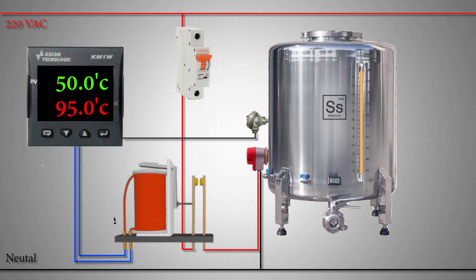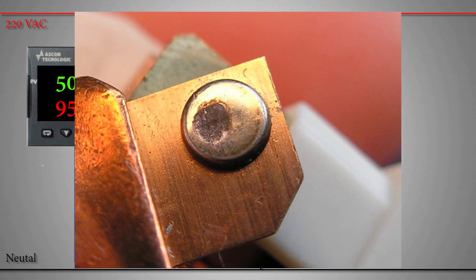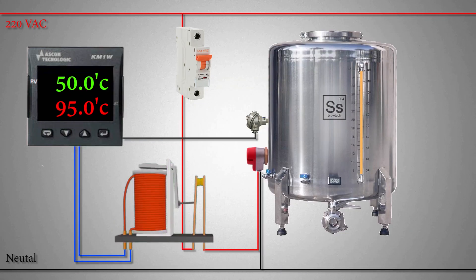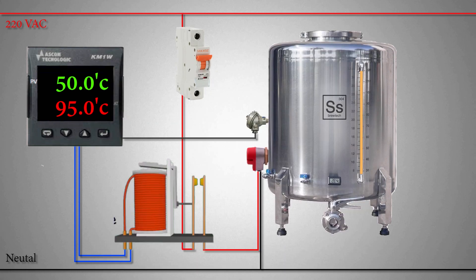But there is a problem with relay contacts. Every time the relay contacts make or break, it creates a spark. Over a period of time, the contacts of the relay get burnt and damaged. In some cases, because of the sparks between the contacts, these contacts can get welded together, and continuous voltage is applied to the heater, causing over-temperature in the tank. The temperature controller can no longer have control over the temperature. So relays are not suitable for switching of heaters and heavy inductive loads.